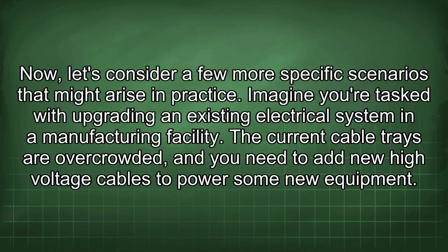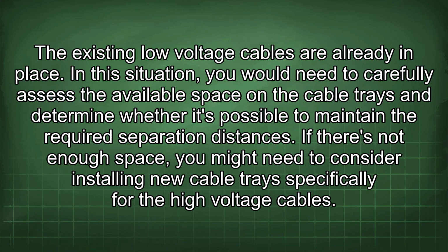Now, let's consider a few more specific scenarios that might arise in practice. Imagine you're tasked with upgrading an existing electrical system in a manufacturing facility. The current cable trays are overcrowded, and you need to add new high-voltage cables to power some new equipment. The existing low-voltage cables are already in place. In this situation, you would need to carefully assess the available space in the cable trays and determine whether it's possible to maintain the required separation distances.